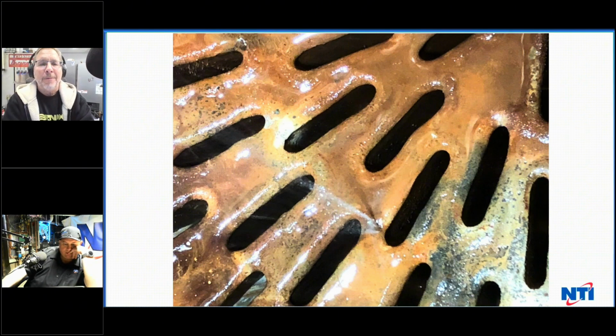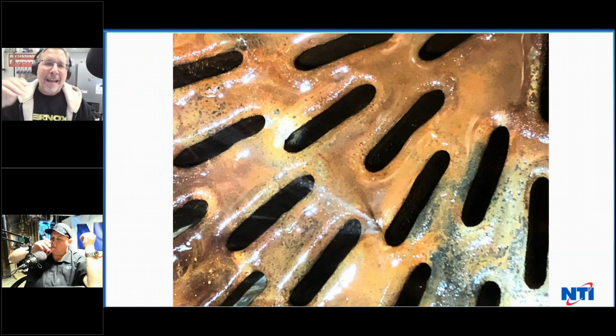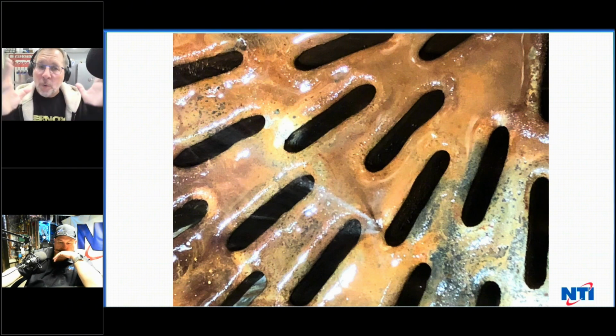I had somebody say to me, well, I'll just get somebody to weld it together. Well, that's great, but all the magnetite's still inside, and it's just going to crack someplace else in hours, not days, not weeks, not months. In hours or minutes, it's going to crack again. So you can't just go weld it. So this is how they fail.